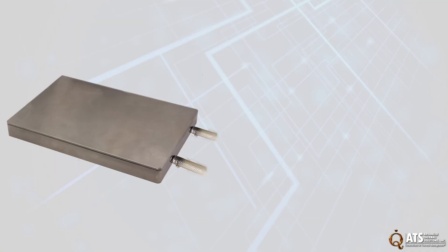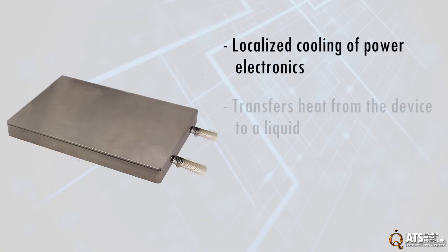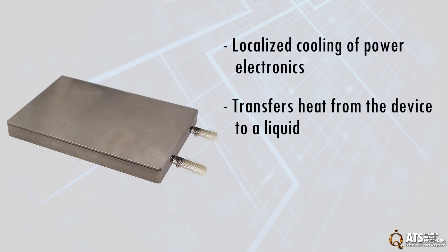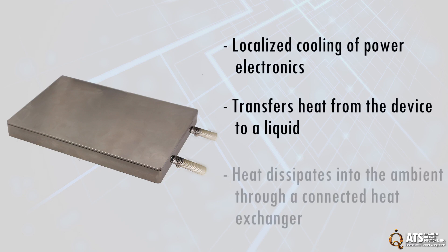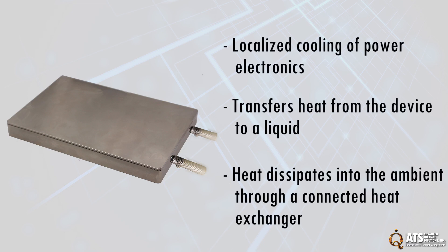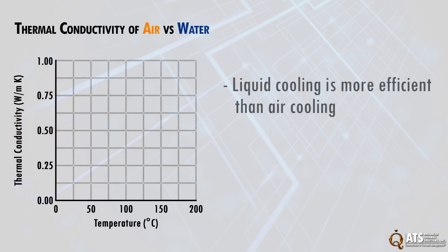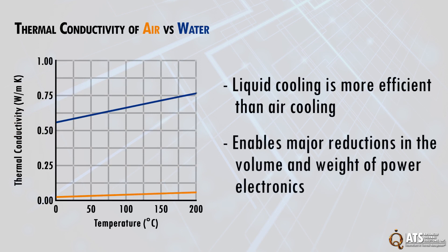Cold plates provide localized cooling of power electronics by transferring heat from the device to a liquid that flows to a remote heat exchanger and dissipates into either the ambient or to another liquid in a secondary cooling system. Compared to air cooling, liquid cold plates provide more efficient performance and enable major reductions in the volume and weight of power electronics.